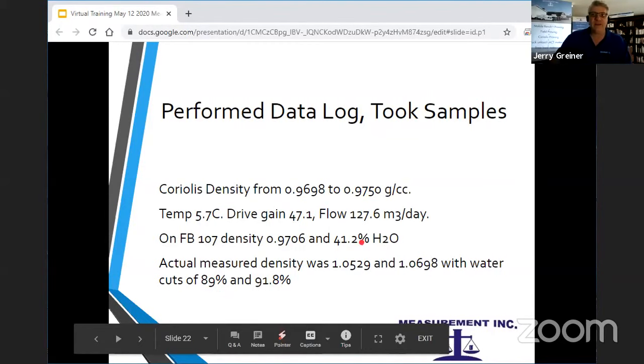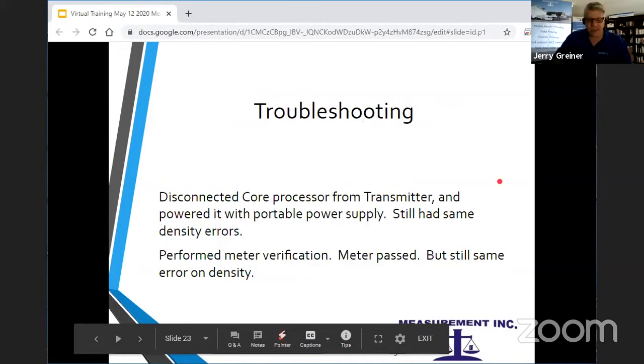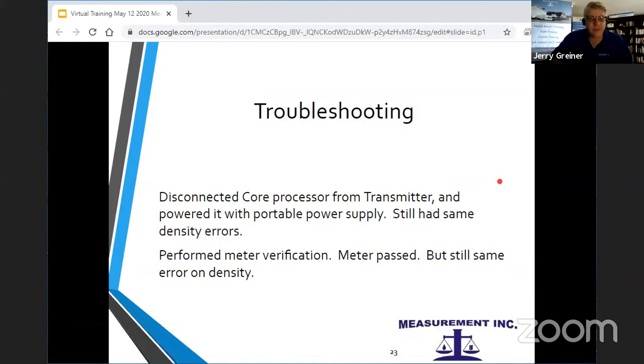So to do troubleshooting, we disconnected the core processor from the transmitter. We powered it with a portable power supply. And some of you guys are more techie, and I know there's lots there that are listening with Ben. You can check the transmitter and everything by just totally disconnecting and powering the core processor directly with the correct power. It's about 12 volts, it's got to be above 11.5. So a battery from a cordless drill works great. And then it's not a transmitter or a power supply or anything else because you can totally eliminate everything else from the system. But with that, we performed meter verification.